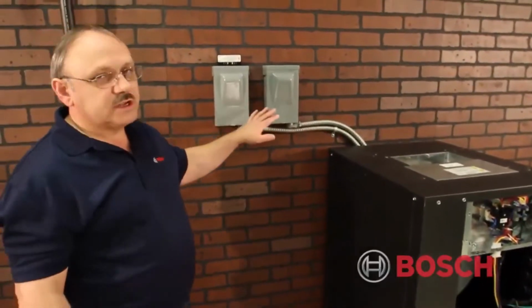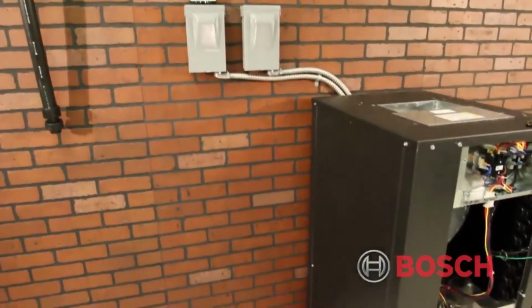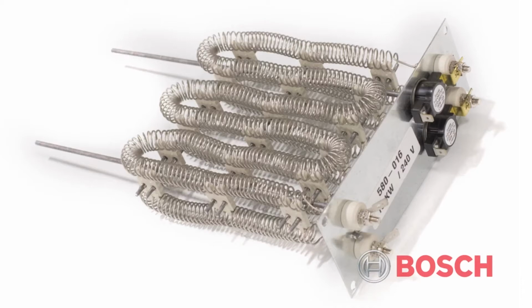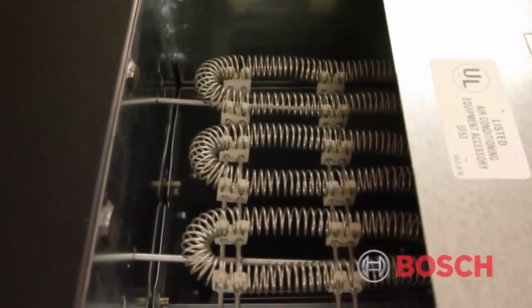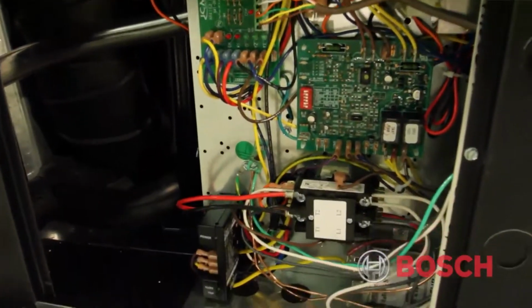All equipment equipped with factory installed electric heaters requires 2 power sources. You'll notice that we have 2 disconnects on the wall. One of the disconnects takes care of power for your heat strips, for your blower operation, and also for all of your low voltage circuits. The other disconnect supplies power to your compressor contactor. At this point, we're going to show you where those connections are made on the equipment.